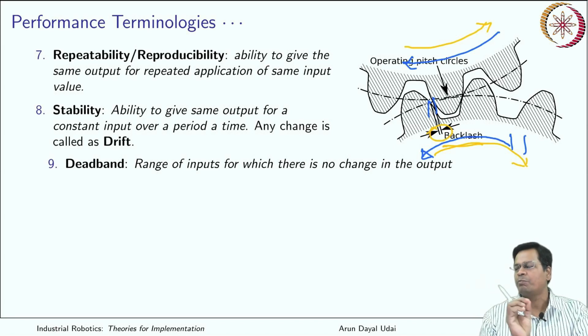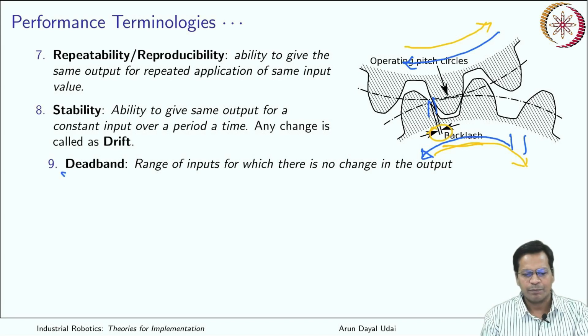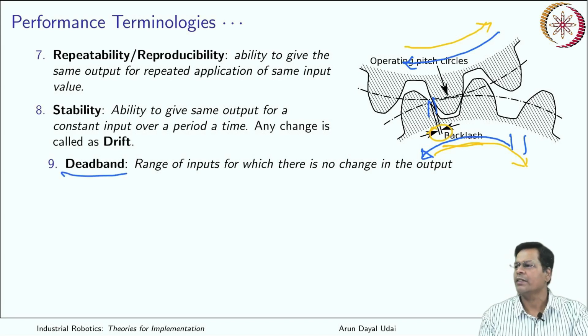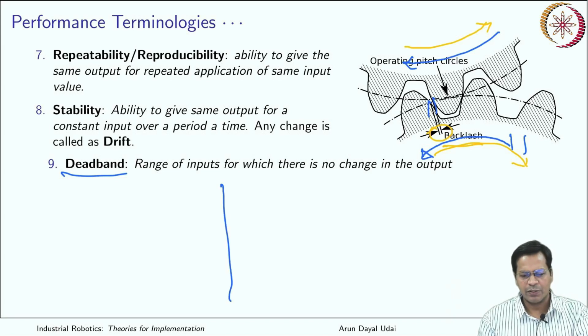So that delay is the dead band, when the output does not change even though the input has changed. That is also present in some sensors. Mostly in amplifiers, you may have a dead band where a small change in input produces no response in the output. Sometimes it is specified as the amplifier picking up only after a period of time. That is the dead band.